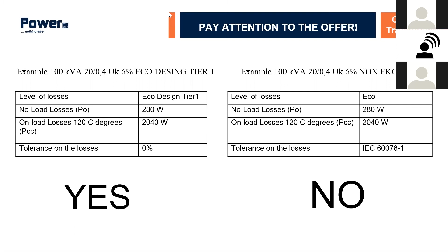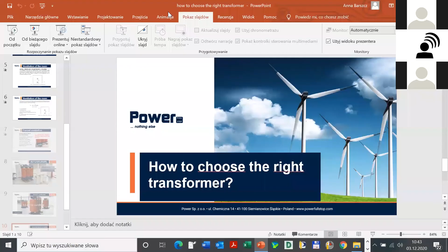On the right side, you can see something which is really not permitted. Somebody is writing 'eco', not 'eco-design'. The losses are eco-design losses, but the tolerances of losses are IEC 60076, meaning plus 15%. So be careful if somebody is playing with this. It shouldn't be offered in Europe, but we found more offers with this problem.